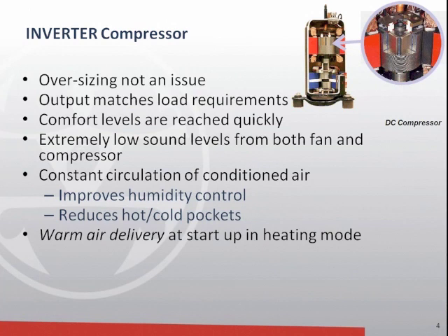In a traditional system, if you oversize it, that means even worse short cycling, even more stress on the system, and uncomfortable conditions inside as the temperature continues to overshoot and undershoot the set point. With an inverter-based device, it simply throttles down to the exact capacity that's needed and continues to operate on an ongoing basis, meeting only the existing need. And so you're not ramping up and down, you're exactly targeting the set point and you're achieving it within half a degree.